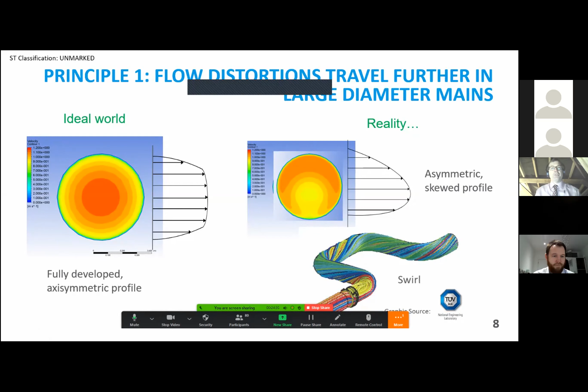So NEL, the National Engineering Laboratory, just outside Glasgow in Scotland, has said swirl can take over 100 pipe diameters to decay. In fact, there have been cases where swirl has persisted for over 500 pipe diameters before the profile returns to exceptionally close to ideal. A really good case study was given in 2007 in the American Water Works Association Journal, where Dick Finesse went down to Brazil. He went to a pump station that had a 48-inch pipe coming out of it, and he showed that 200 diameters downstream from this last disturbance, you could still get a distorted flow profile, so swirl was still persisting. So in larger mains, flow distortions do travel longer.